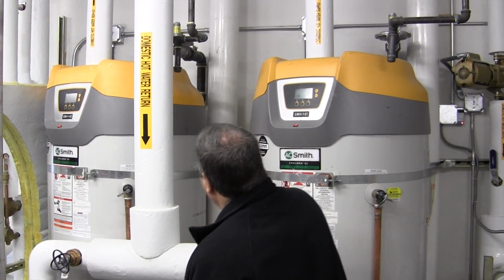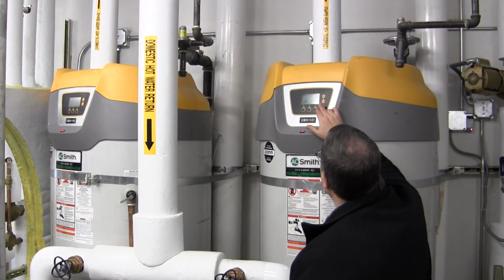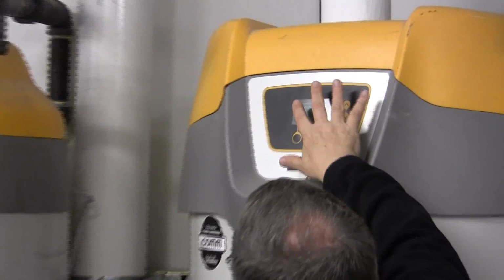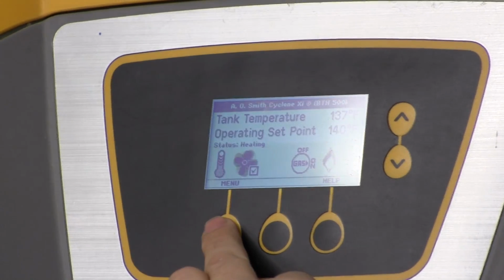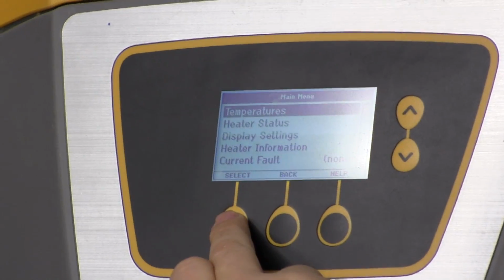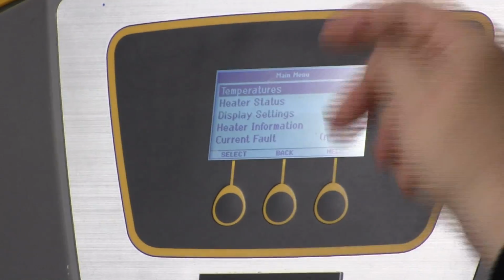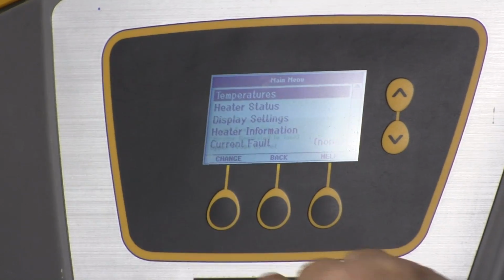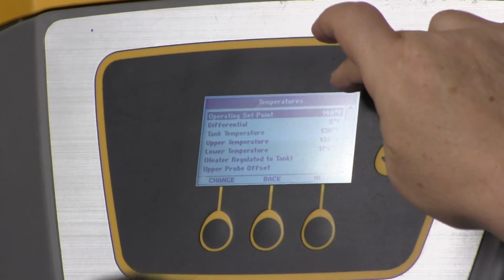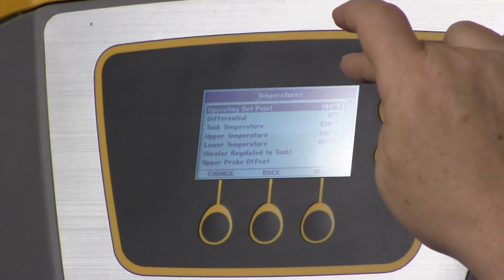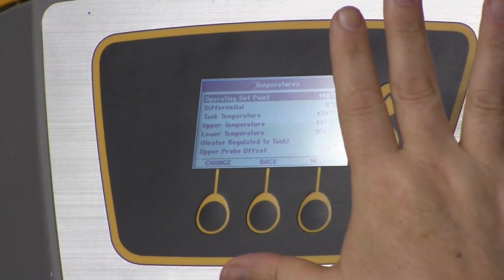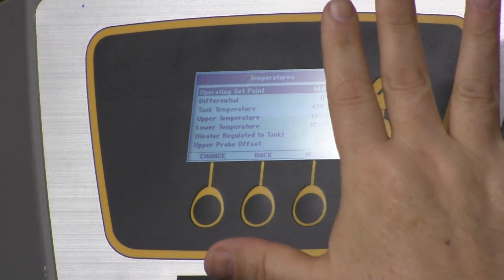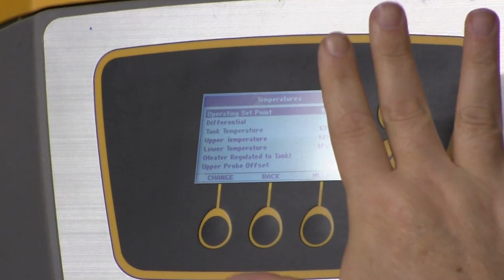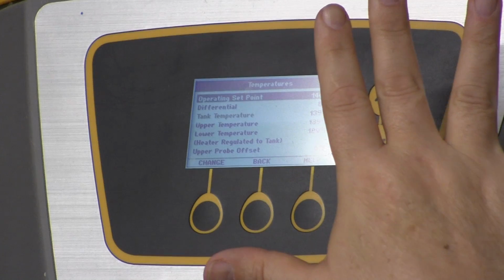Well, the heart of this unit is the control, and if you see there's a button here that says menu. If you hit menu, it's going to give you different things you can go into. The first one is temperatures. So if you select temperature, you'll see that the operating set point on this is 140. So this unit is making 140 degree water. 140 degree water can burn people, so my assumption would be that there's a mixing valve somewhere.